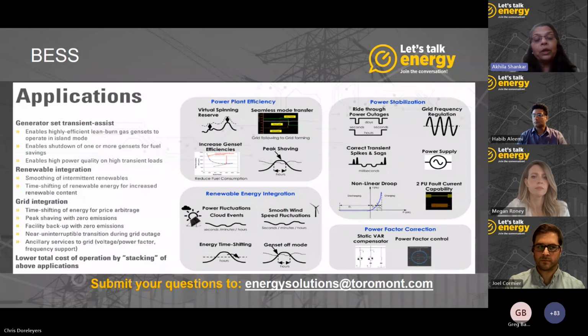And BESS, when it is used with the utility grid, allows for time shifting of energy for price arbitrage. That is, it allows determination of the best source that should be supplying power to the loads for the lowest cost of energy. BESS can also provide immediate response to grid disturbances, helping maintain voltage and frequency stabilities.